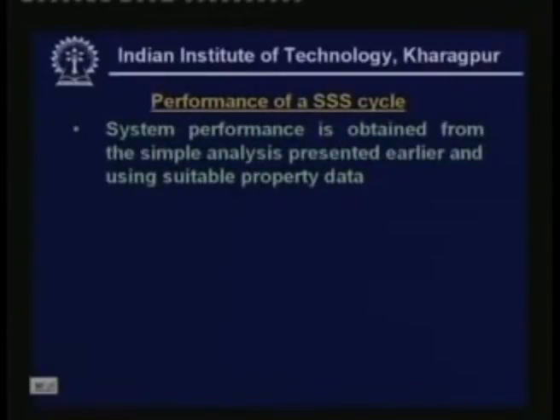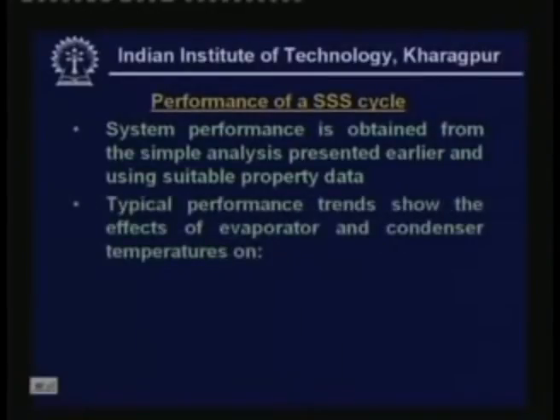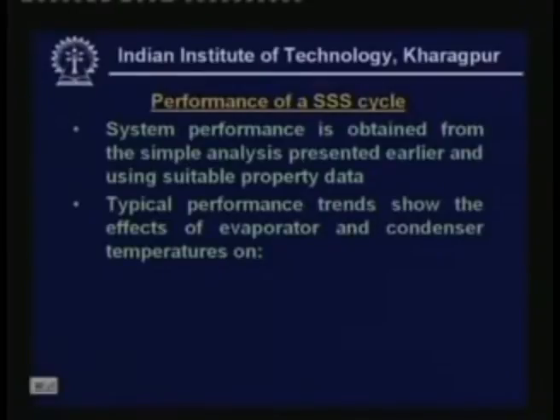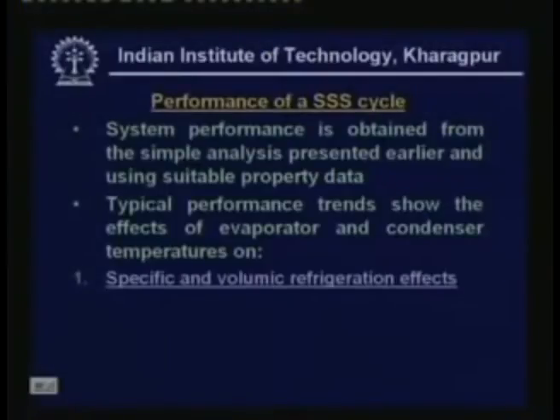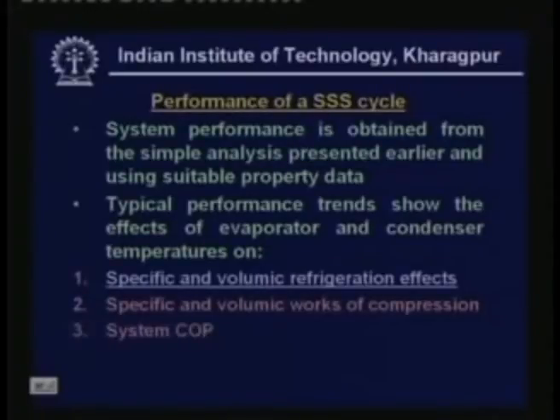Let us begin with the performance of SSS cycle. The performance can be obtained from simple analysis presented in the last lecture using suitable property data. Typical performance trends show the effects of evaporator and condenser temperatures. Normally we keep the condenser temperature constant and vary the evaporator temperature to find different performance parameters, then keep the evaporator temperature constant and vary the condenser temperature. In this manner we can find the effect of both condenser and evaporator temperature on performance parameters including specific and volumic refrigeration effects, specific and volumic works of compression, and system COP.